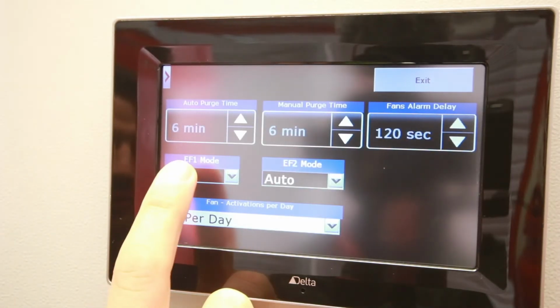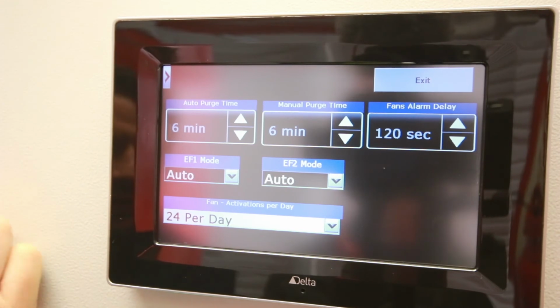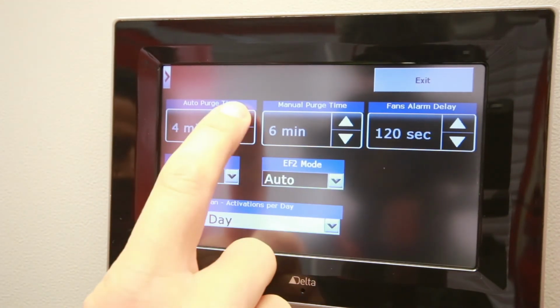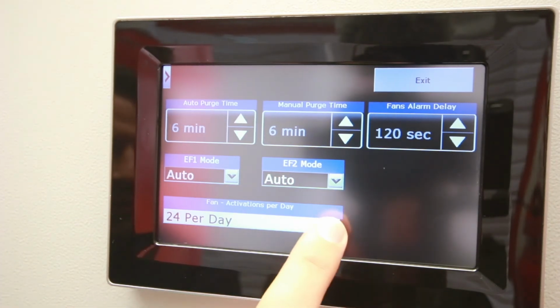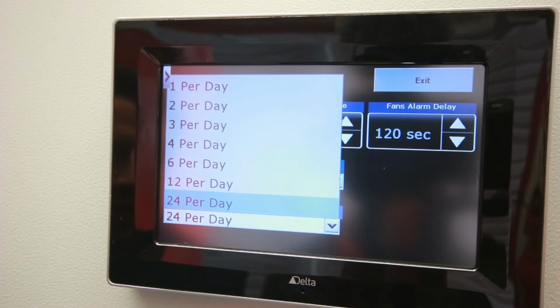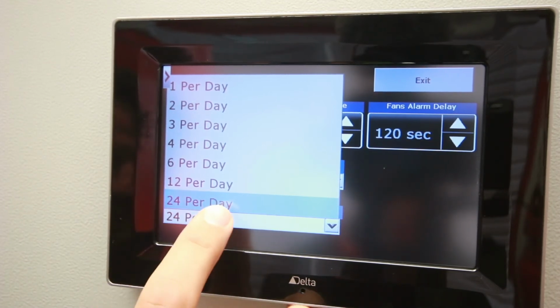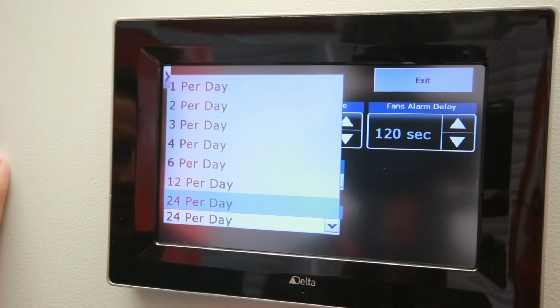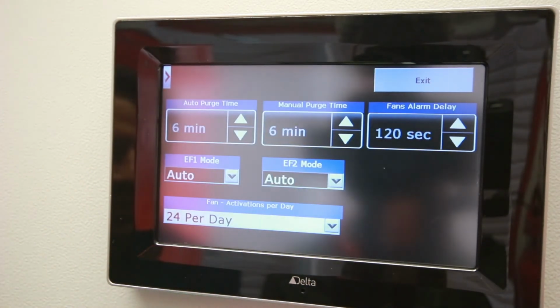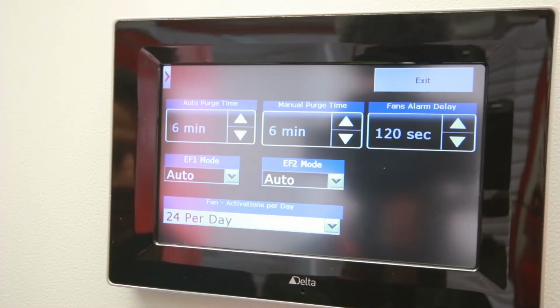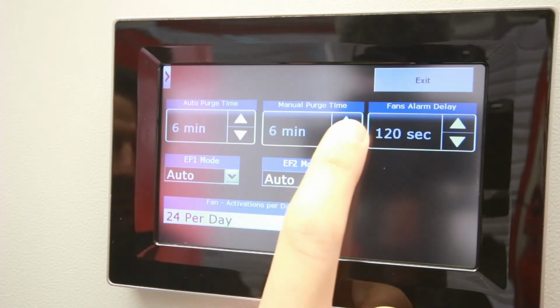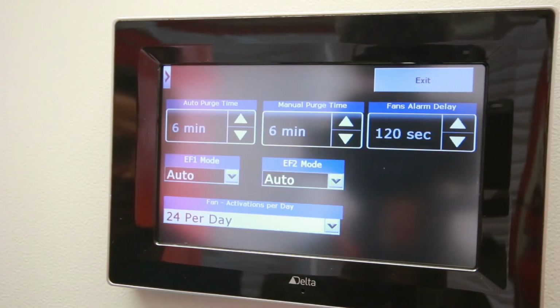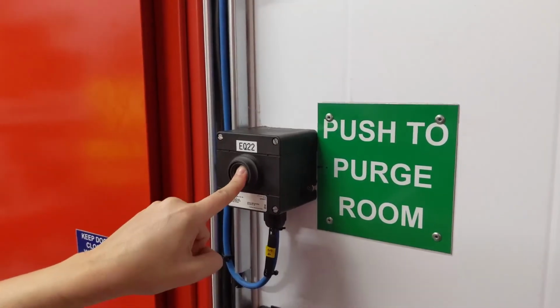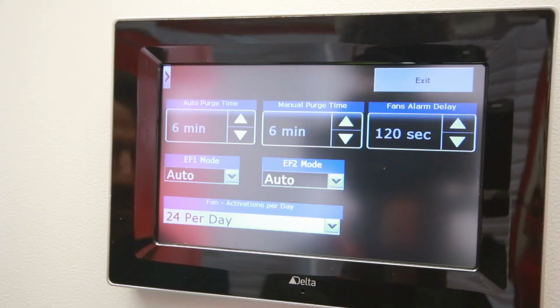Now we'll look at the advanced settings. Here we have our two extract fans, EF1 and EF2. The auto purge can be adjusted as such. The auto purge simply kicks the fan on a fixed number of times per day. 24 per day will be once an hour, 12 per day will be once every 2 hours, and so on. This means the extract fans are automatically kicking in at a predetermined time frequency. The manual purge time can be adjusted as such and is operated by the pushing of the button inside the store to initiate the extract. Return to the menu by hitting Exit.